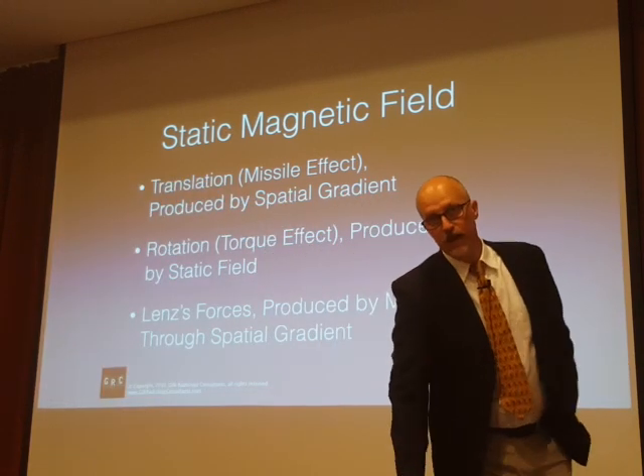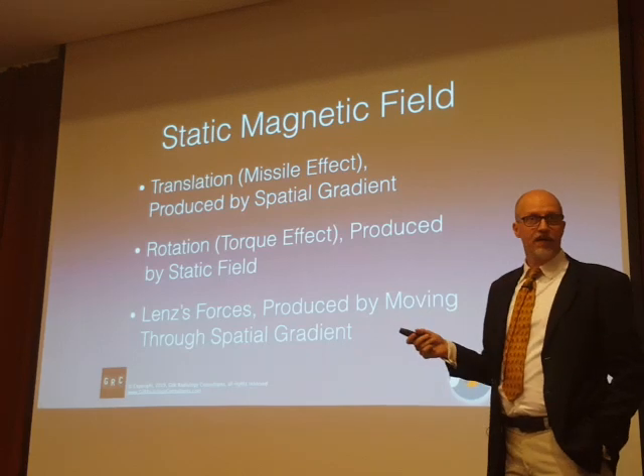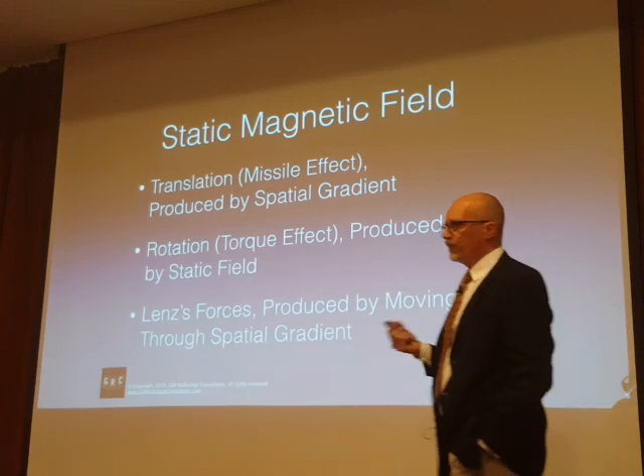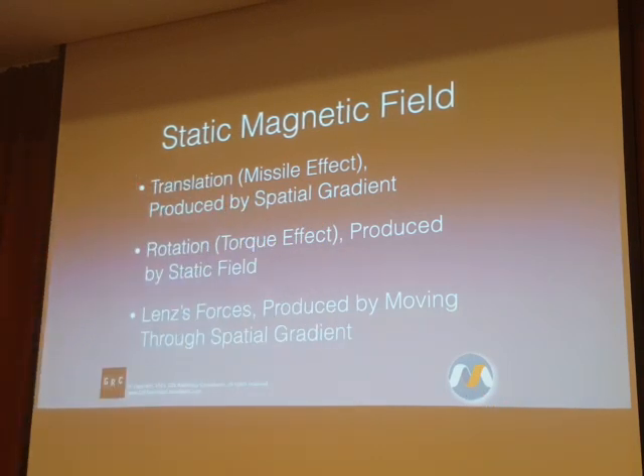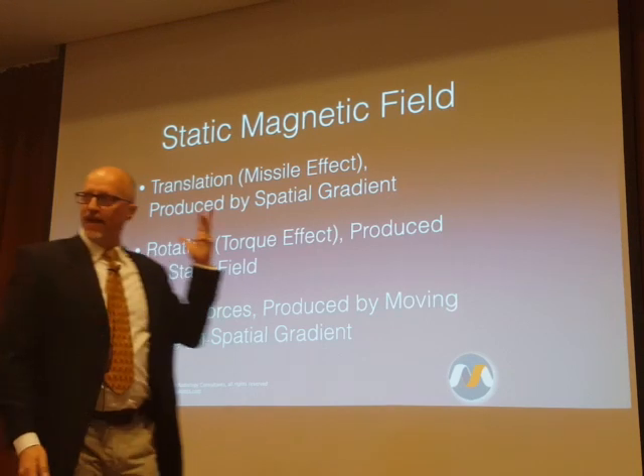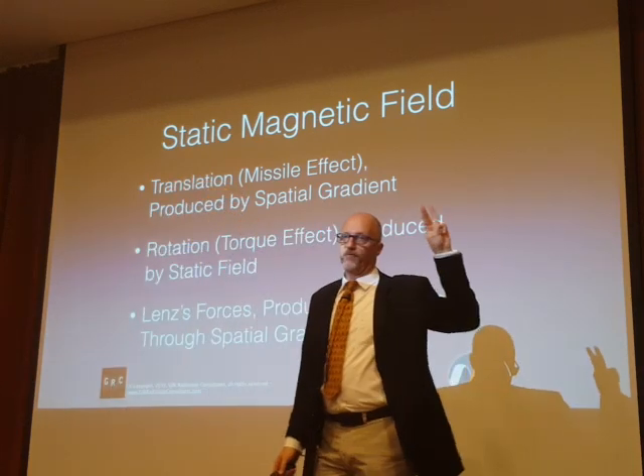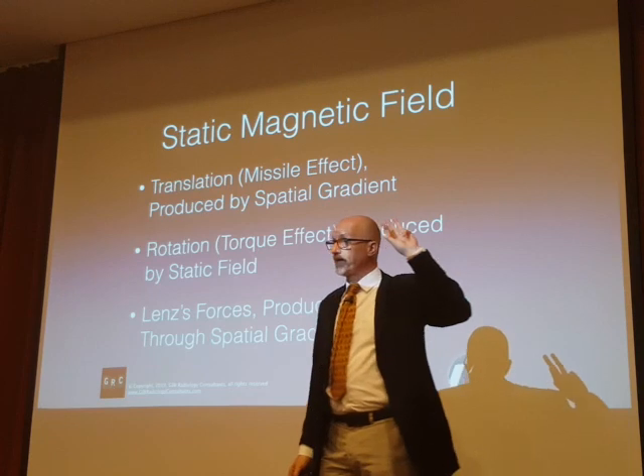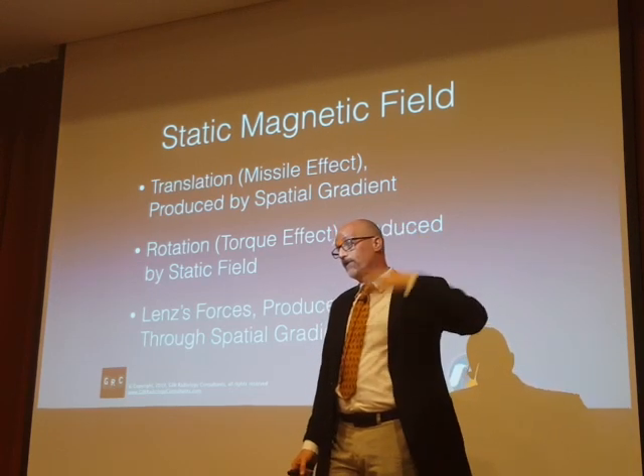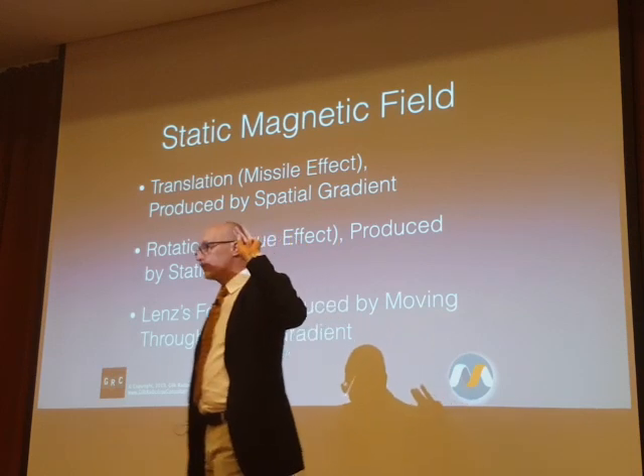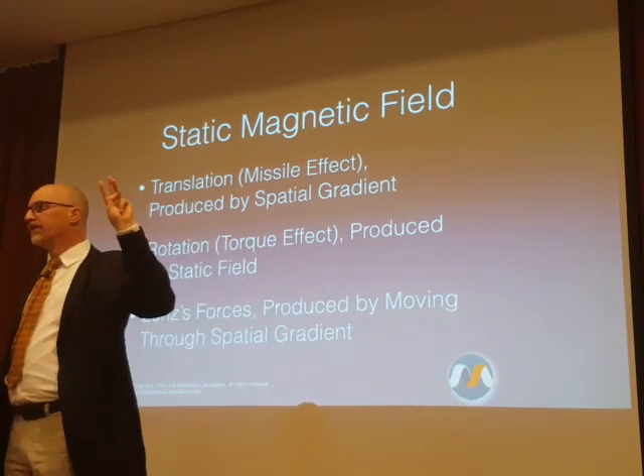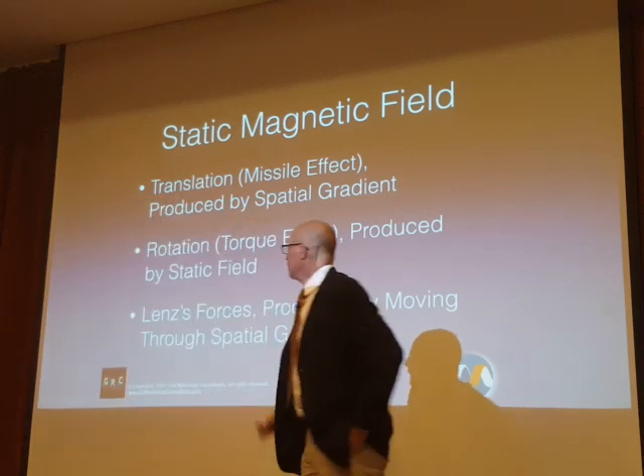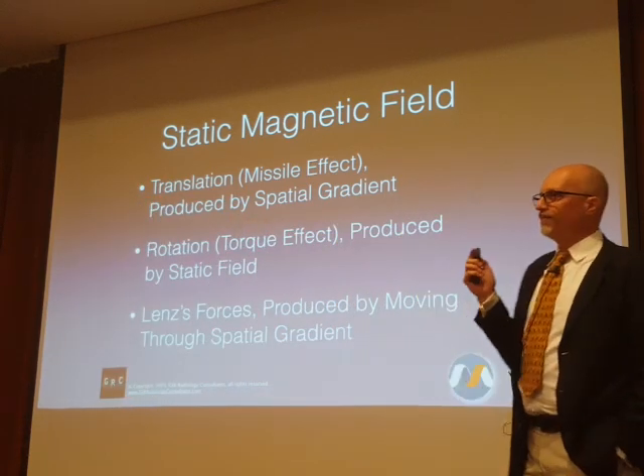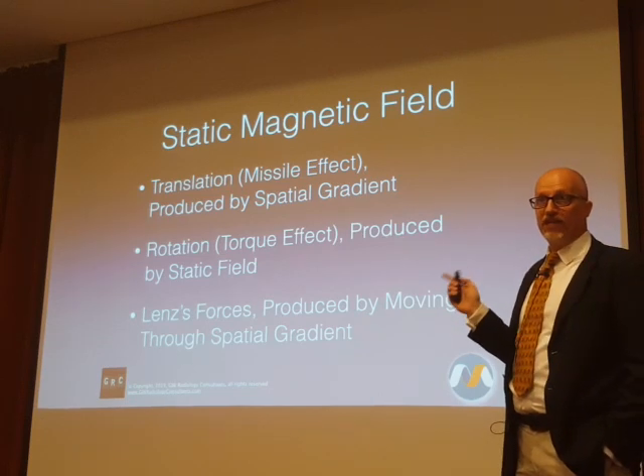Lenz's effects are not terribly common, both because we usually aren't moving very large objects close to the magnet, and when we are, we're generally moving fairly slowly. It's rare that we have this magical combination of the three factors: a large electrically conductive object moving in the steepest portion of the spatial gradient and doing so very rapidly. So lens effects are interesting, not very frequently a safety issue.